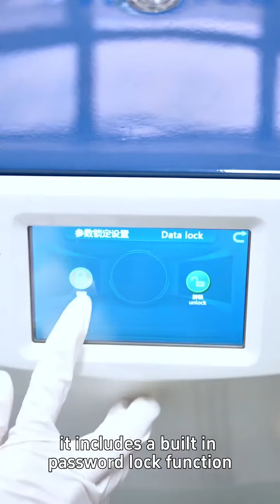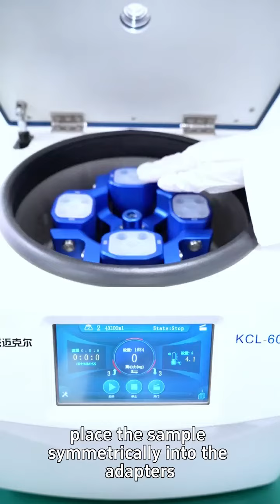Next, take a look at the inside of the device and press the door open button. The centrifuge has a built-in leveling device. You can adjust the device's level status at any time. Before using the new centrifuge, remove the fillers from the inside. Place the samples symmetrically into the adapters. Close the door, and the device enters the running state.